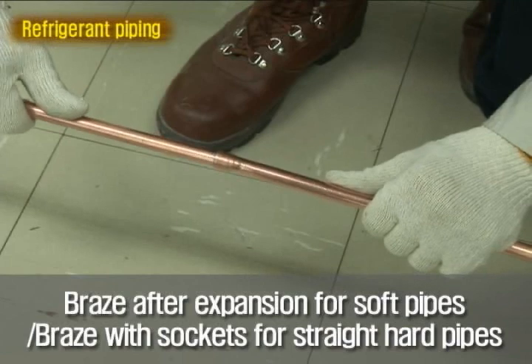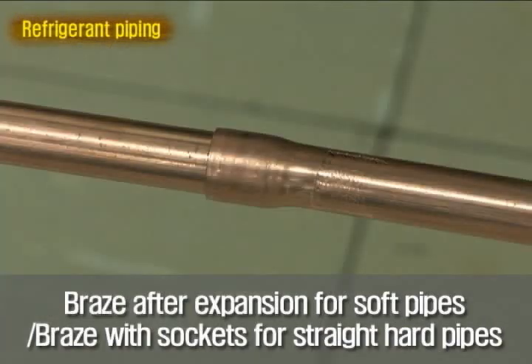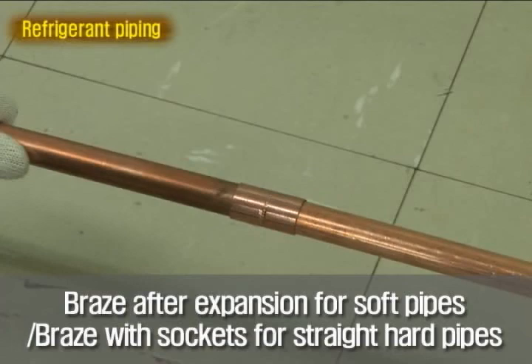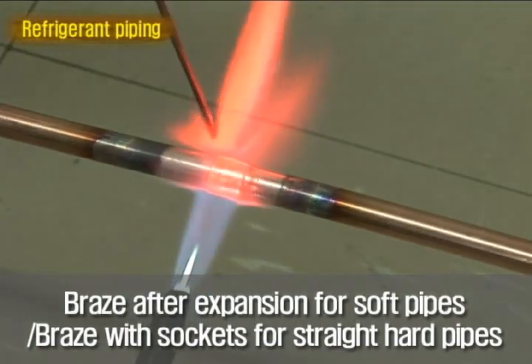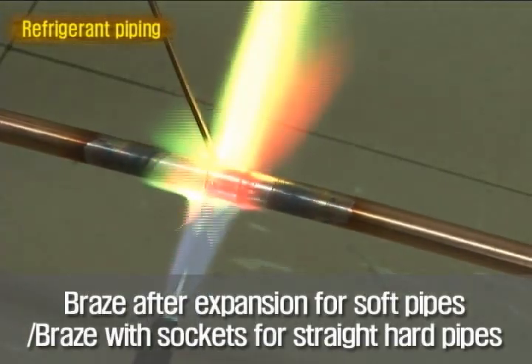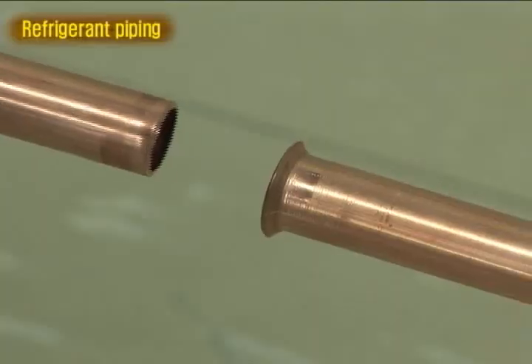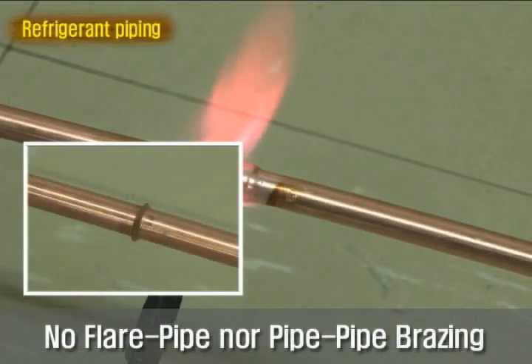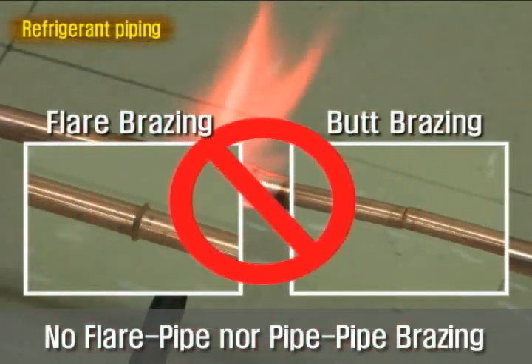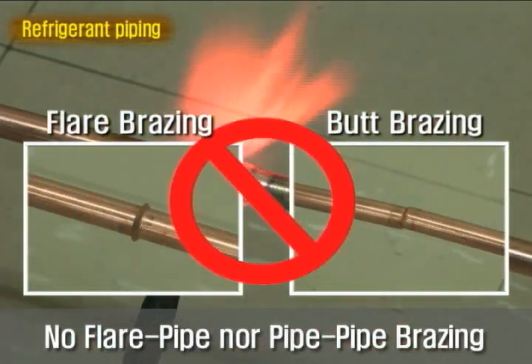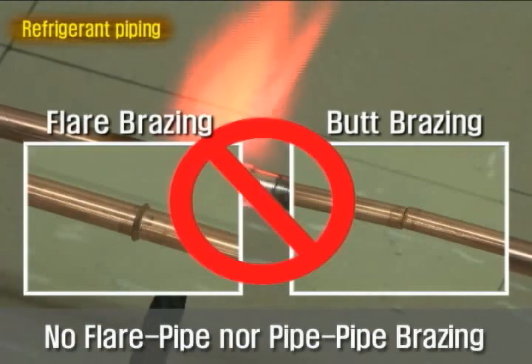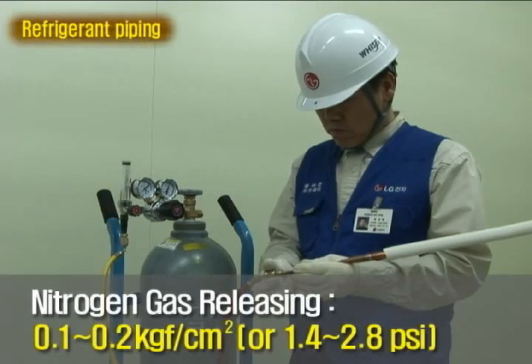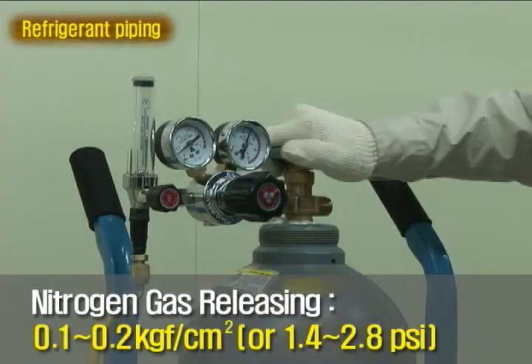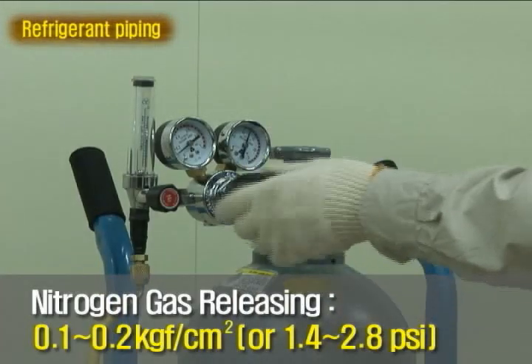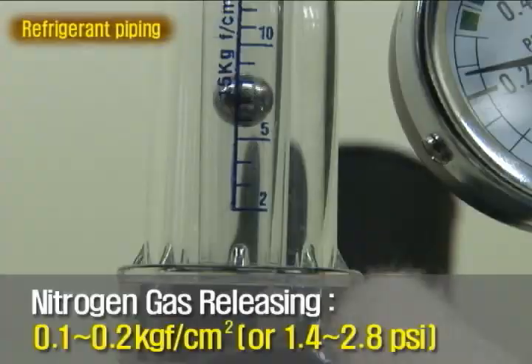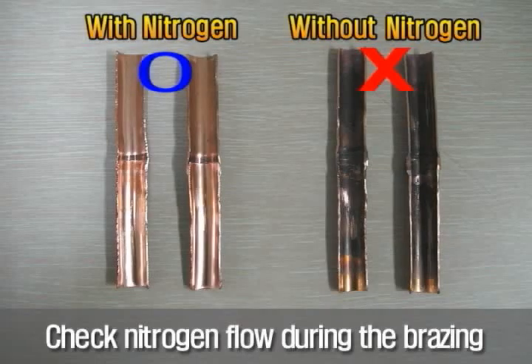For extension of copper pipe, expand it for soft pipes or use sockets for straight hard pipes, and make sure the pipe is overlapped sufficiently. The brazing of flare to pipe and pipe to pipe without overlapping can be easily damaged. Avoid this kind of brazing. Nitrogen gas should be released during the copper pipe brazing to prevent oxidation. Oxidized particles can block the pipe and cause compressor defects.